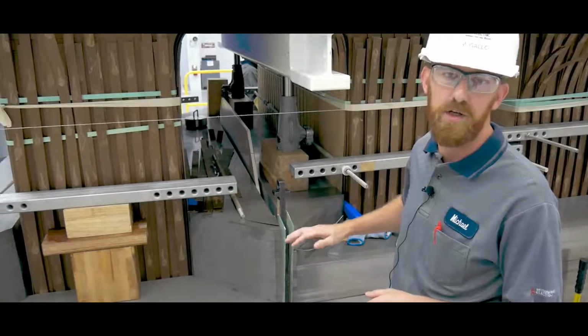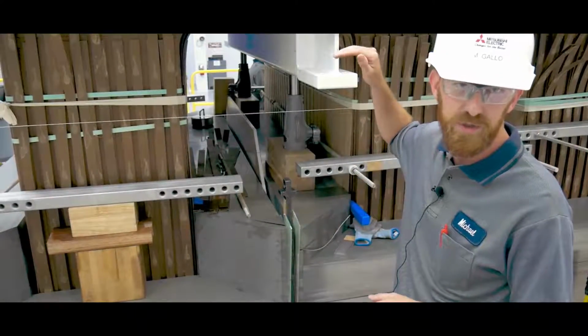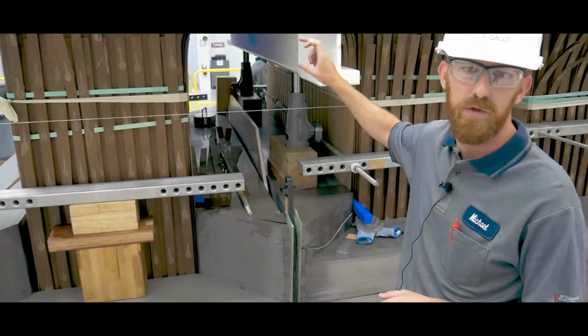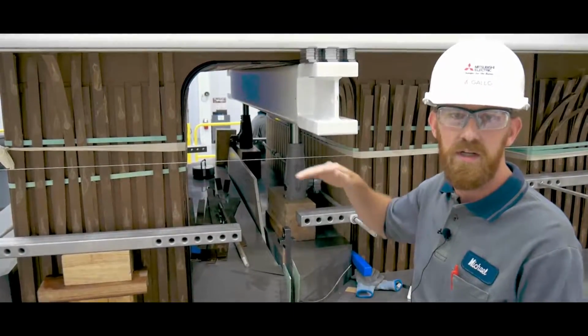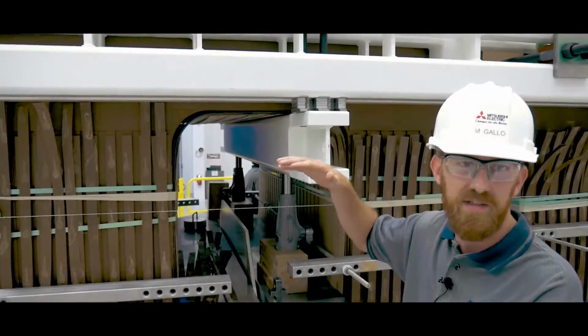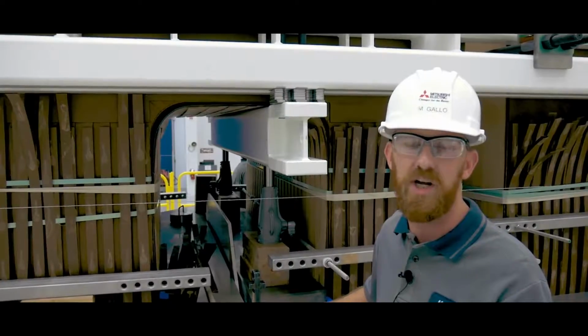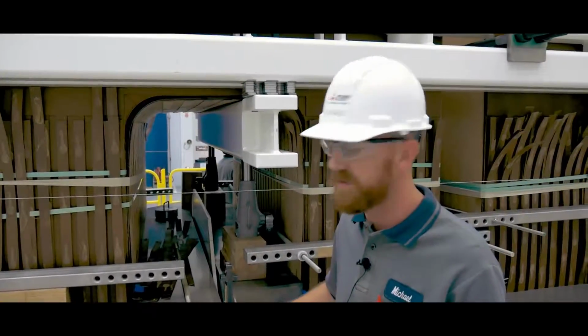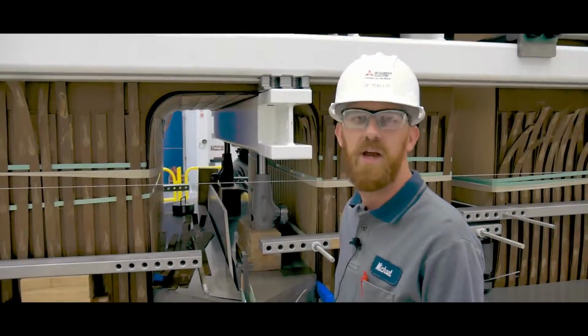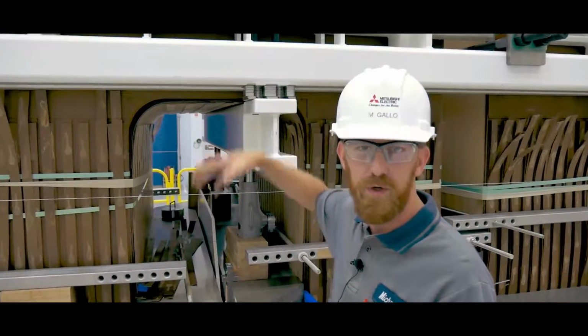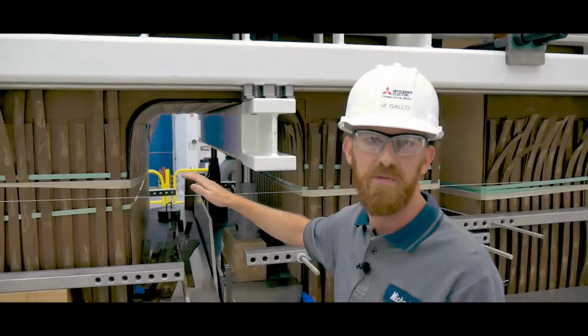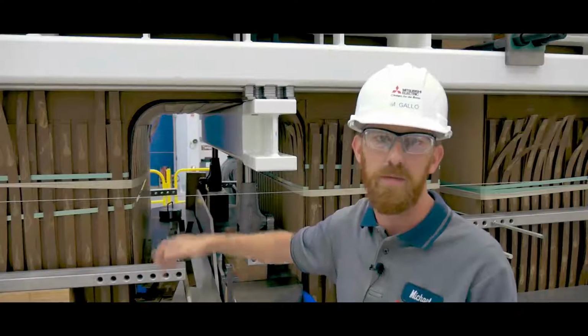After the steel has been completed, we drive a wedge into the remaining space between the coil group and the top of the steel, to pressurize the steel down so there's no movement during transportation or during operation. From there, the upper tank will be put on, and it'll be sent to the next department for welding and external pieces to be added.